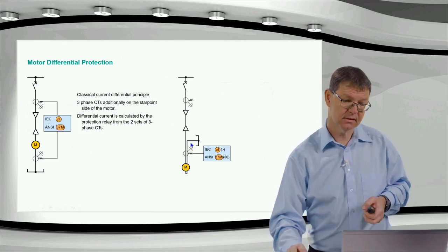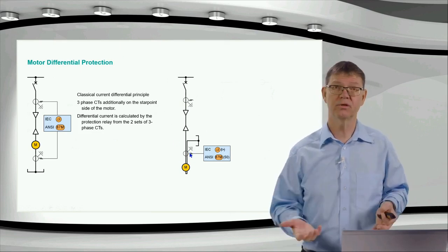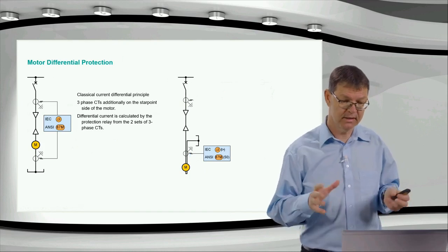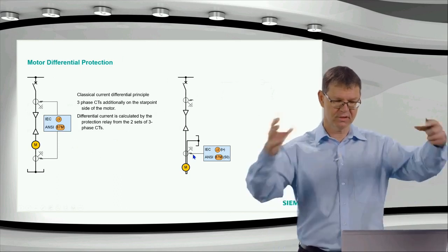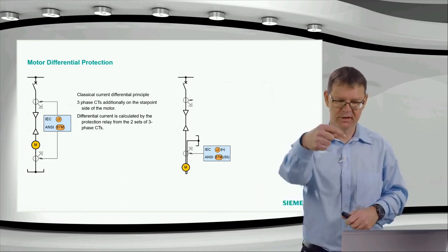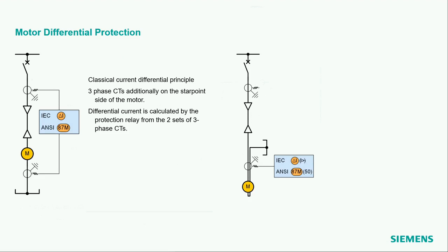And with this current transformer, a so-called window type current transformer, basically behind this symbol we have three single phase transformers, transformers with a hole inside, and they will bring the current of phase one in one direction through that current transformer, and you go back again before you make the star point. Okay, the backwards cable is not going through the motor again, so maybe that's not correctly drawn. It goes around and you guide it back, and we have three of them.